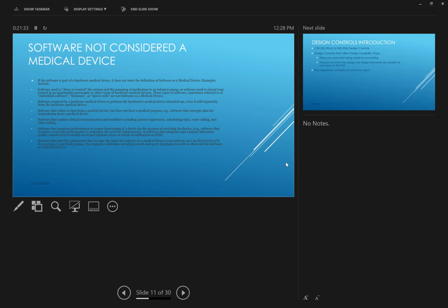Sure. So there's also a process we'll talk about. Is it de novo, right? There's some cases where if you go onto the FDA website and you're pretty clear on your intended use and what your product does, there's things about your product codes, right? We won't get into this in this presentation. You see things like FDA product codes. Those FDA product codes are basically associated with the risk class. So if you know what your device is, and you have a predicate device, and it's been proven out there that that predicate device is pretty similar to your device, you will fall under that product code in that risk class.